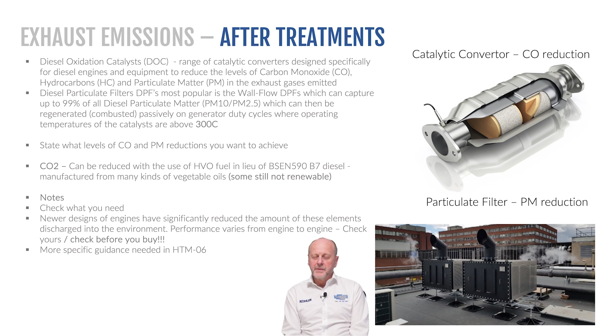You need to check what you need, but more specifically, the guidance stated in an updated HTM06 needs to be very clear on what these requirements are. It's important, though, to know that there is a limit to what can be added to the output of a generating set. Every element that you add adds back pressure to the engine, but one of the most important factors is that all these catalytic converters only function correctly when they are hot, and in order for them to get hot, the engine needs to be working at a high level of load.